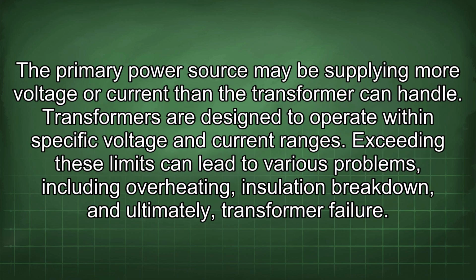The primary power source may be supplying more voltage or current than the transformer can handle. Transformers are designed to operate within specific voltage and current ranges. Exceeding these limits can lead to various problems, including overheating, insulation breakdown, and ultimately transformer failure.